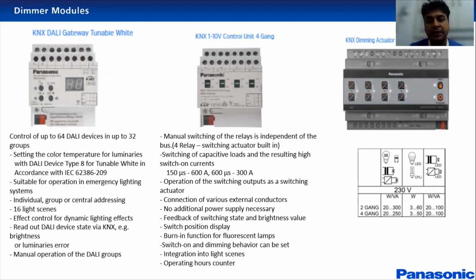You can control your human-centric lighting using this. Again, this is a single-channel one: 64 DALI devices, up to 32 groups, and 16 scenes can be created. We have a 1 to 10 volt control module, 4-channel, so 4 control voltages are provided. Along with this, you also have 4 switching relays built in, so you can create RGB or RGBW scenarios and control them using this.